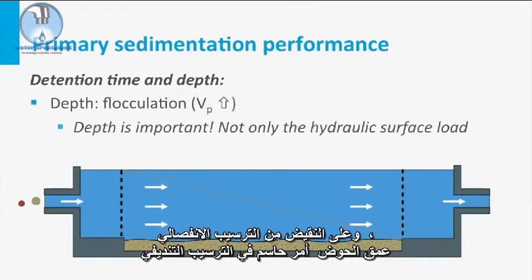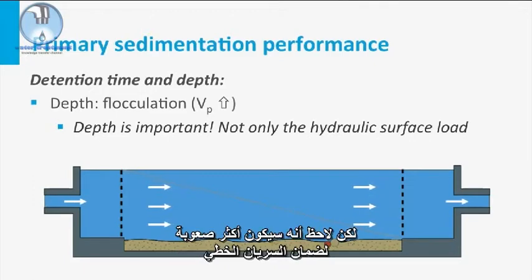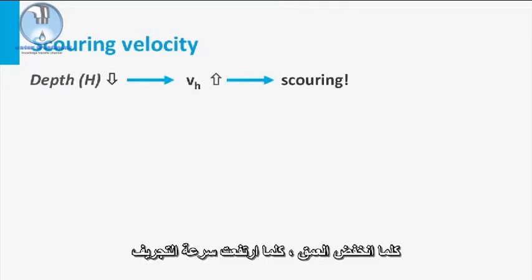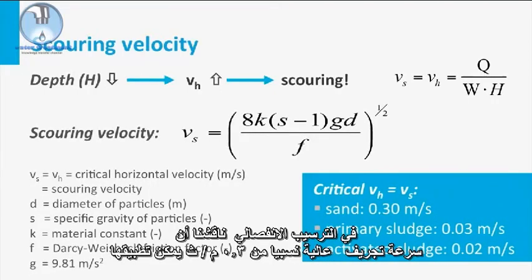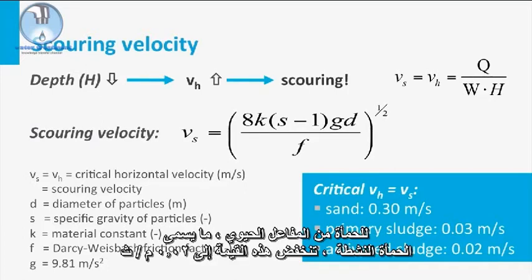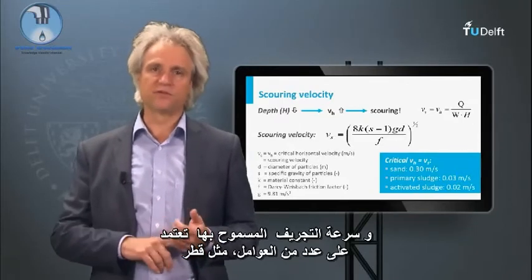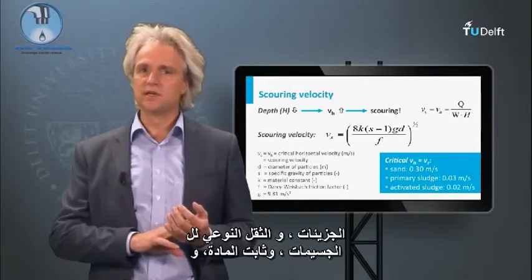In contrast to discrete settling, the tank depth is crucial in flocculent settling. A higher depth enlarges the chances for flocculation as illustrated in the slide, but note that it will be more difficult to guarantee laminar flows in deeper tanks. The depth of a tank is determined by the allowable scour velocity or the maximum allowable horizontal velocity. The lower the depth, the higher the scour velocity. In discrete settling, a relatively high scour velocity of 0.3 m/s is applicable to separate sand from organic solids. For primary sludge itself, the maximum scour velocity is about a factor 10 lower, so 0.03 m/s. For sludge from the bioreactor, the so-called activated sludge, this value drops to 0.02 m/s. The allowable scour velocity is dependent on factors such as the diameter of the particles, specific gravity of the particles, material constant, and the Darcy-Weisbach friction factor.